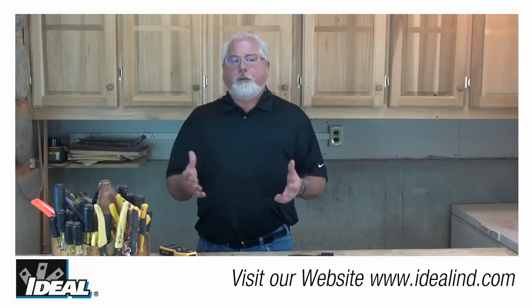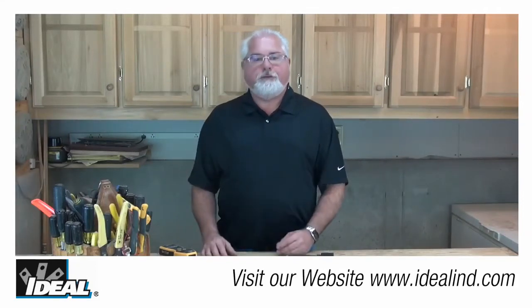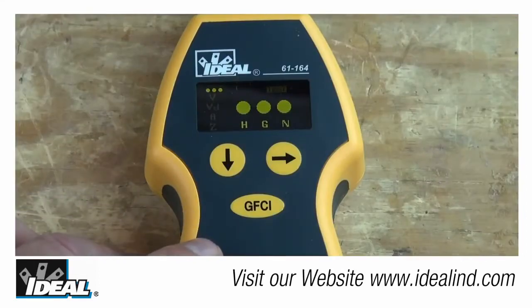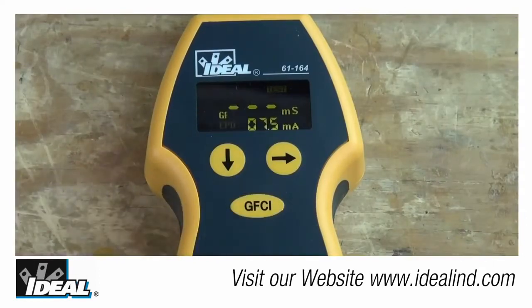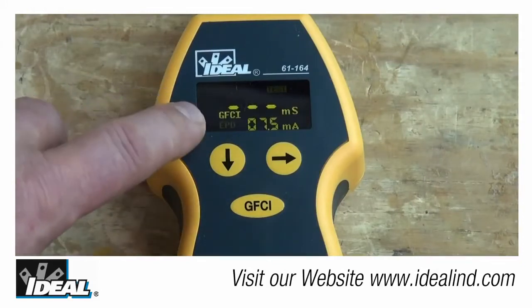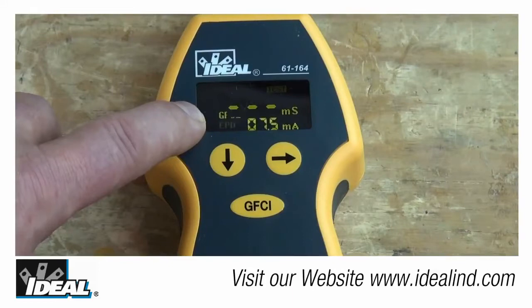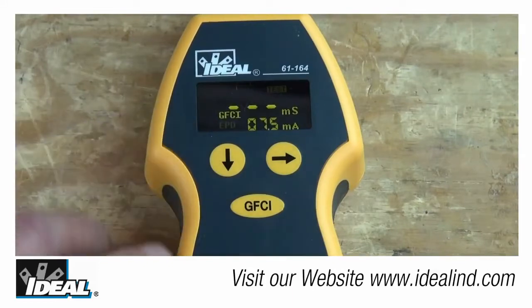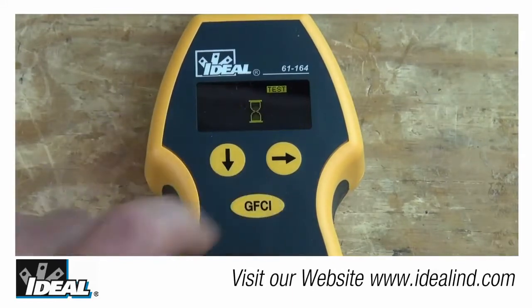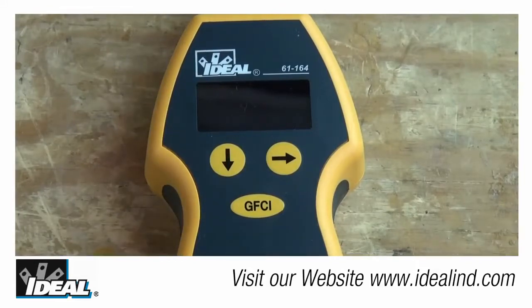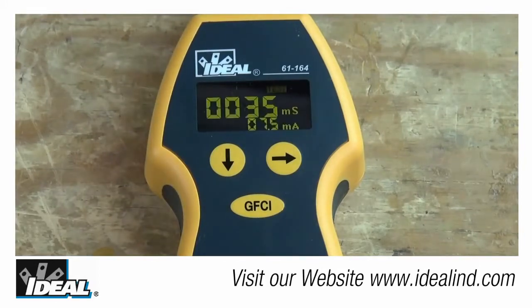Now, the tester is going to display the actual test current in milliamps and the trip time in milliseconds for you. And to very simply conduct a GFCI test, press the GFCI button to enter that GFCI main menu. The GFCI symbol in the display should be highlighted as the default test. Then simply press the GFCI button once to activate the test itself. Now, the actual current being leaked to ground is displayed, and the test icon and hourglass symbol appear on the display to let a user know that the test is being performed.